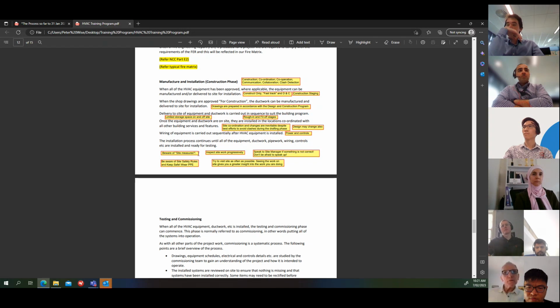So I'm rambling on, but these things can happen. With site measures, in a place where I used to work, we had a policy that any site measures required would have to go through engineering first before they were allowed to be made in the factory. Quite often what happens is a site person sends a sketch straight to the factory, gets it made, sent to site, and they install it. The first thing you hear about it is something's not working properly, or it's noisy, or we can't get the airflow. And when you look at it, that's different to what we designed.